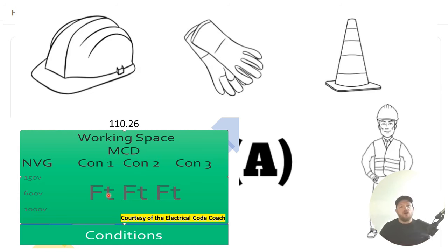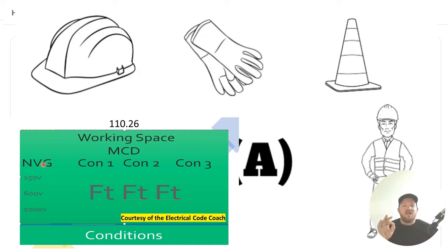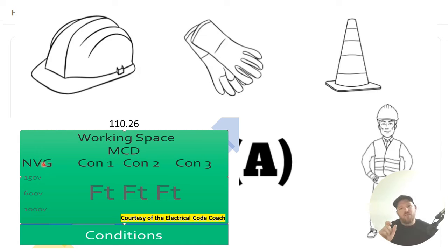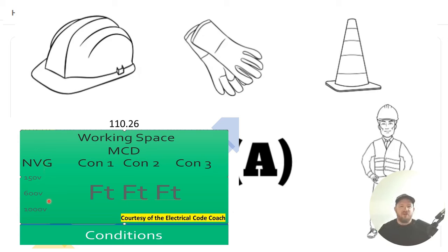Let's go ahead and answer our question for today. First, let's start with our nominal voltage to ground. Well, ours was 480/277. But we're only going to be working with that lower number because that is our highest voltage to ground in this case. So we're going to come here and it's going to fall into this middle column, if you're between 151 volts and 600 volts.